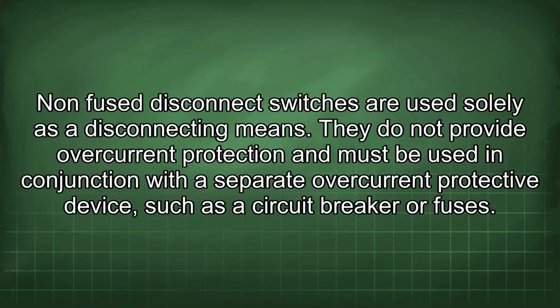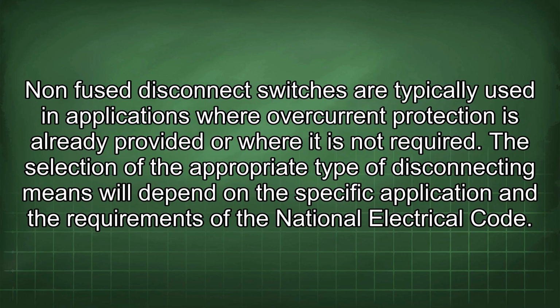Non-fuse disconnect switches are used solely as a disconnecting means. They do not provide overcurrent protection and must be used in conjunction with a separate overcurrent protective device such as a circuit breaker or fuses. Non-fuse disconnect switches are typically used in applications where overcurrent protection is already provided or where it is not required.